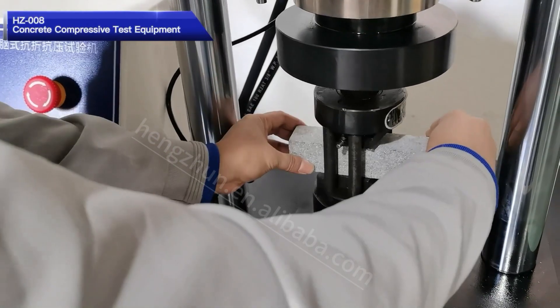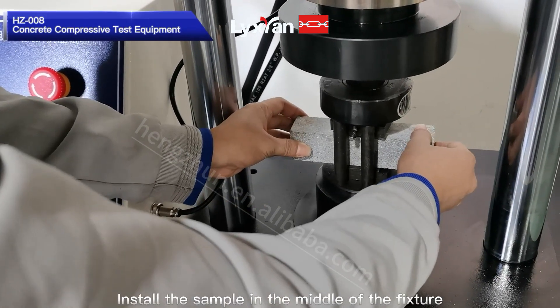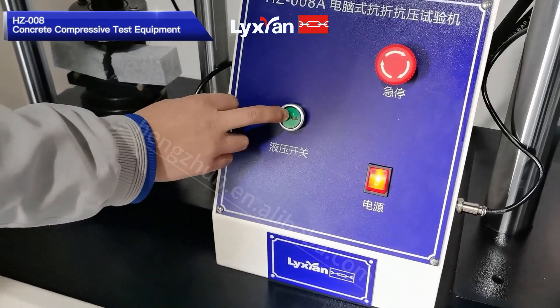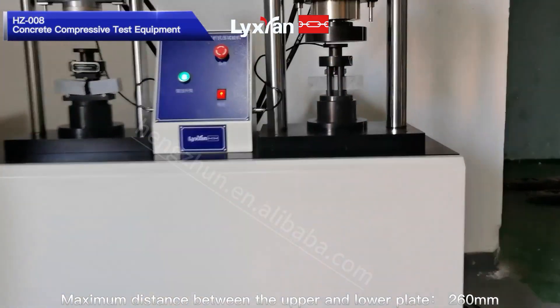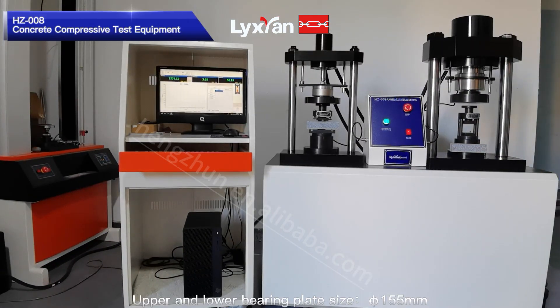Concrete Compression Test Machine HZ-008 Concrete Compressive Test Equipment. Install the sample in the middle of the fixture. Maximum distance between the upper and lower plate: 260mm. Upper and lower bearing plate size: 155mm.